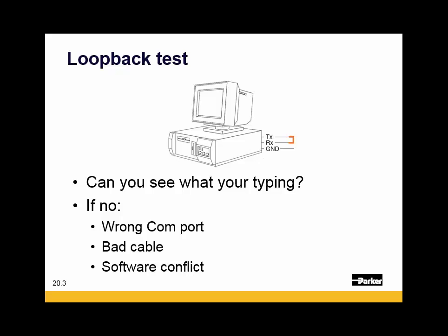Or some other product or some other software has control of the COM port, so go in your task manager, make sure everything else is turned off. On Windows 98 and 2000 operating systems, the Allen Bradley RSLinx software would start automatically on power-up and always grab control of the COM port. So go ahead and double-check that that's not running and shut it down if you need to.